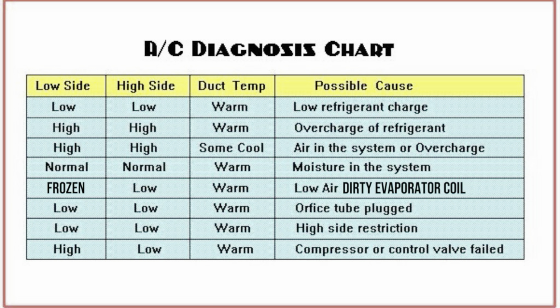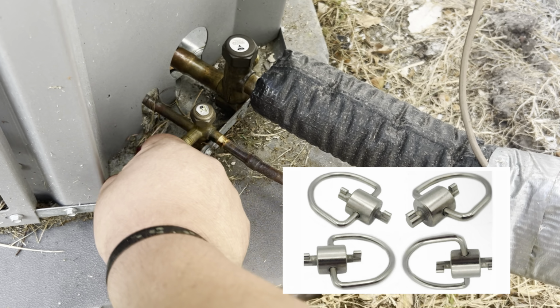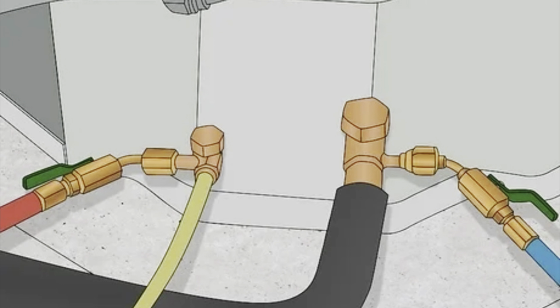Now that you know where your pressure should be, you can use this chart to help you diagnose further what the issues could be, based on what the low side and high side give you. Before hooking up your gauges, you will need this refrigerant key to remove the refrigerant caps, as they are installed in every single unit. Again, the blue line goes on the bigger suction or low side, and the red line goes on the smaller liquid or high side.